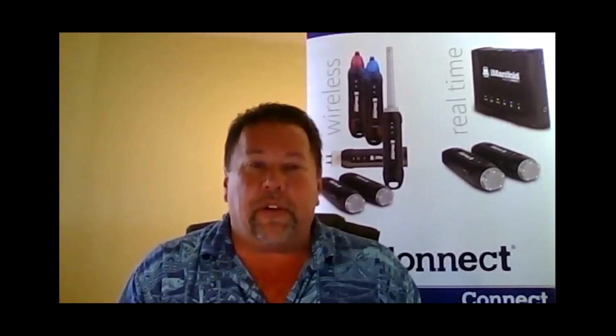With variable speed systems, depending on the unit, they've got what's called charge mode, where you slip it into charge mode so it runs at full capacity. That way you can get the charge proper, since it's running at full capacity, that's where you pinpoint your charge. These variable rate systems running at half mast need to be charged at full capacity to get it right.